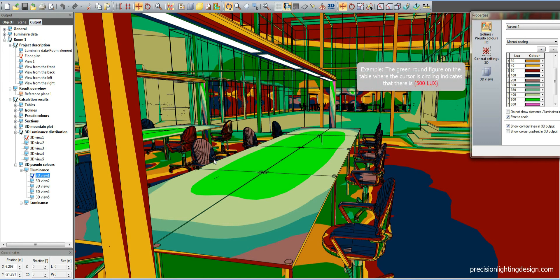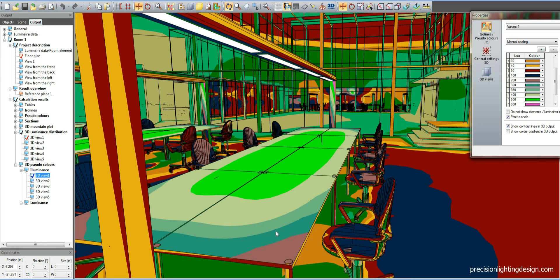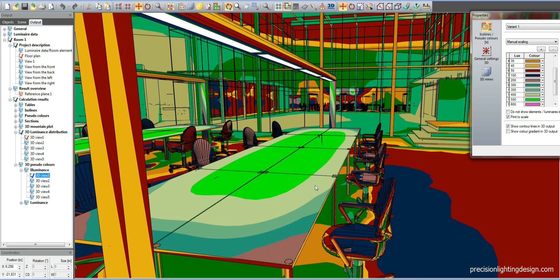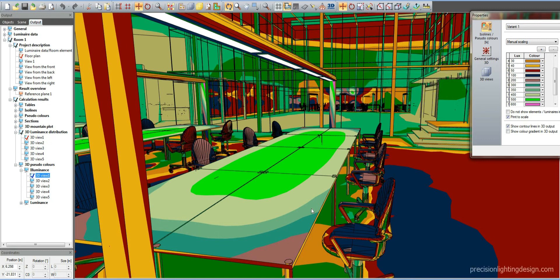The green round color on the table shows that there is 500 lux available on that specific area. The light green color where the cursor is circling indicates that there is 400 lux. There is 350 lux available on the corners of the table. There is 100 lux on the chairs, shown with blue color.